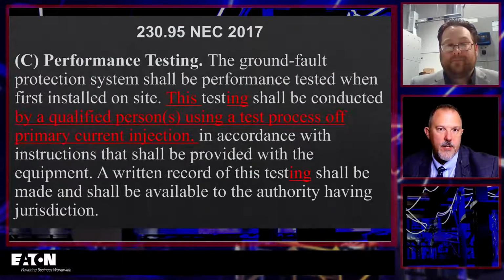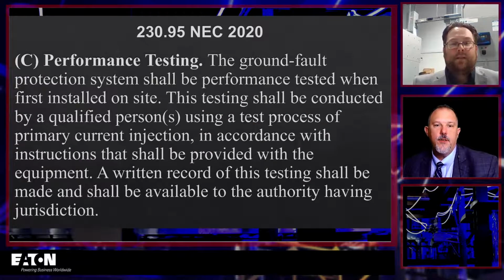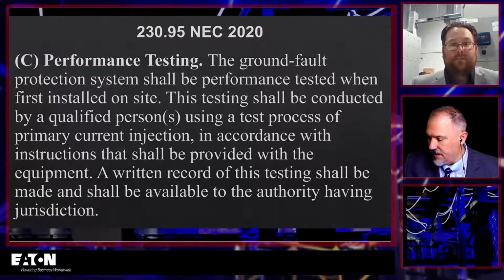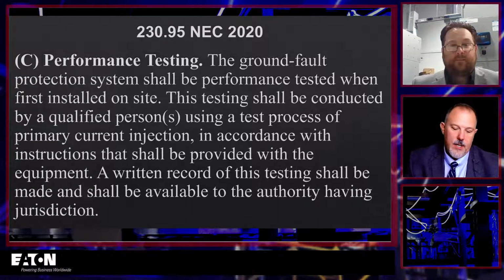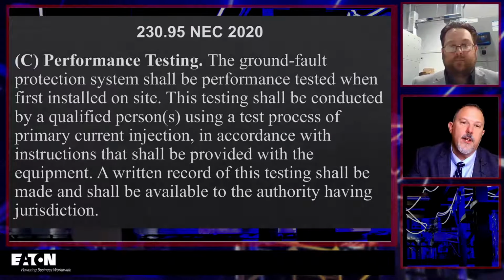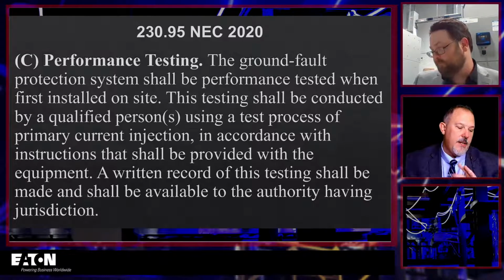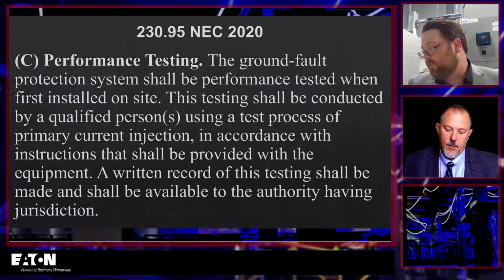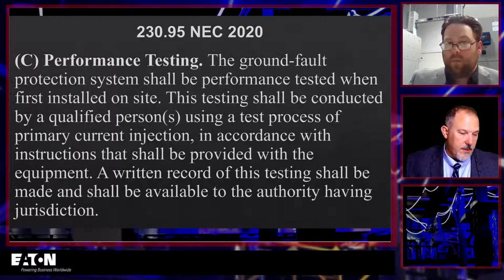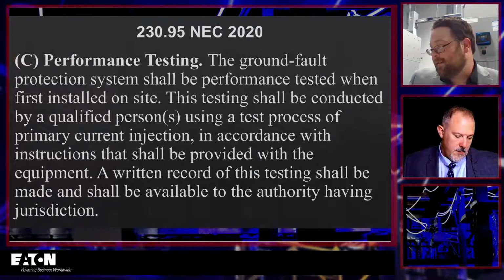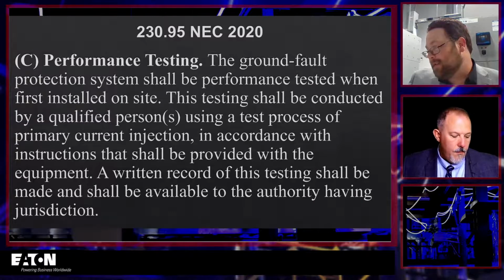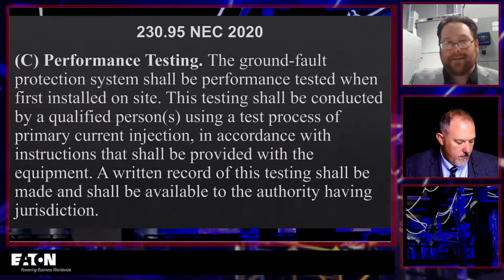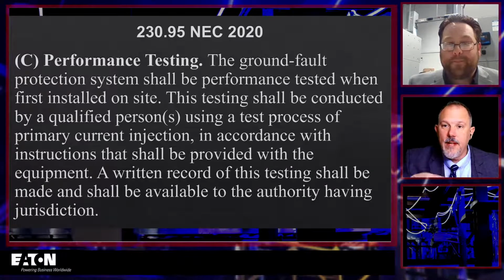Yeah, and you think about the National Electrical Code requirement in 230.95, right? So in 230.95, this is the 2014 code. Let me look at the 2020 code. So in 230.95, you're required to have ground fault protection of equipment. If it's a grounded system, and with the right voltages. I've got it right here, Tom. I've got 150 volts to 1,000 volts, phase to phase, and 1,000 amperes. Right. So we really narrowed it down to grounded.